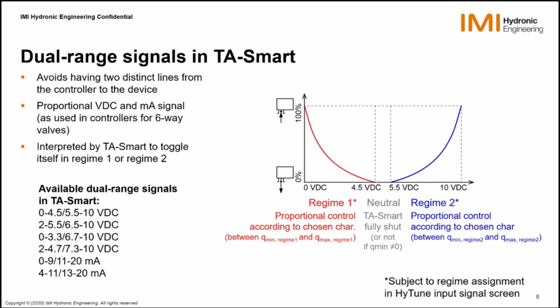Forgot to mention, but the fact that we have a neutral area is important. This is to avoid that at some moment in the year, the valve would constantly switch between heating and cooling and would therefore create a switching in the system that would not be a very good thing for the people that are dealing with the control system. And if associated actions are programmed in the system, you could simply get an issue with the wearing of the associated equipment, be them relays or whatever.